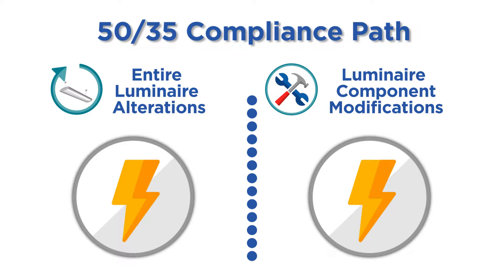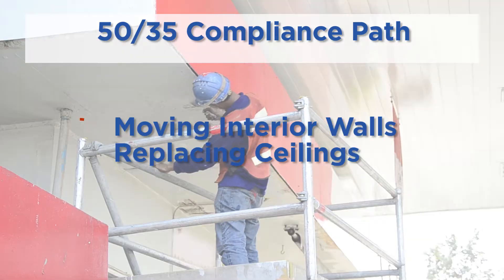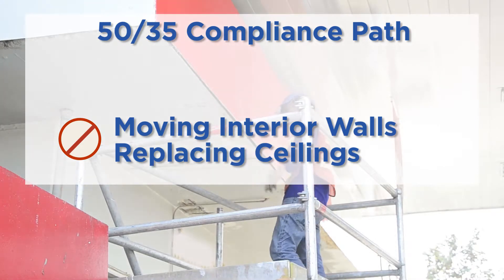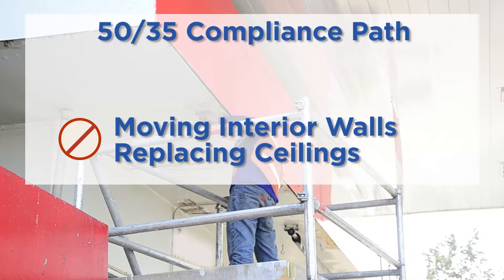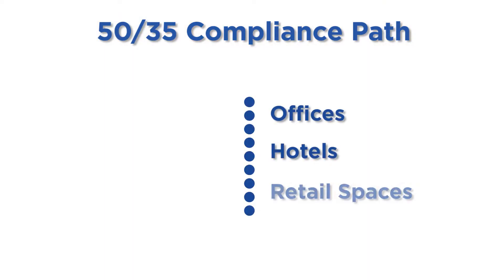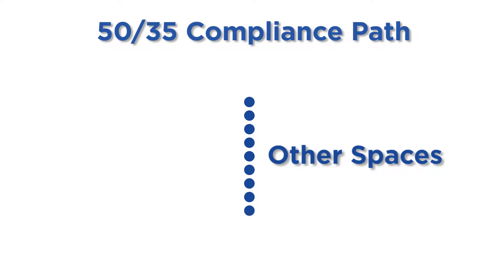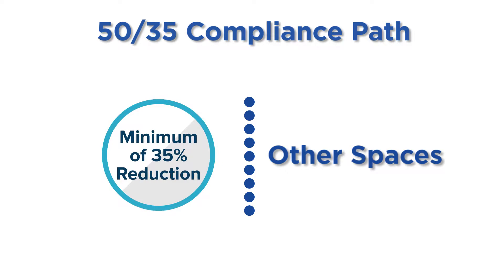This is a new compliance path for 2016. It's important to note that for this compliance path, no redesigning of the interior space, like moving interior walls or replacing ceilings, can be made. In offices, hotels, and retail spaces, the total combined wattage of the altered or replaced luminaires must be at least 50% lower than the existing luminaires. In all other spaces, the total combined wattage must be at least 35% lower than the existing luminaires.